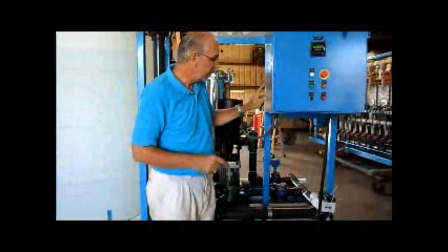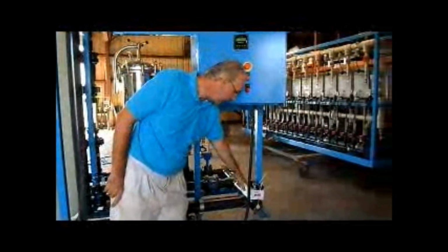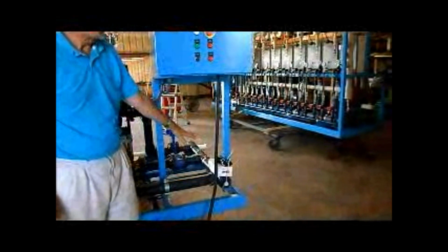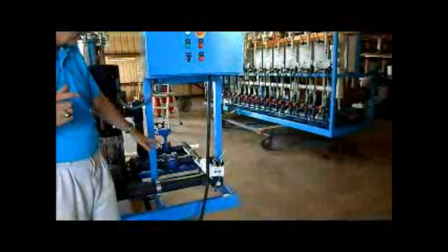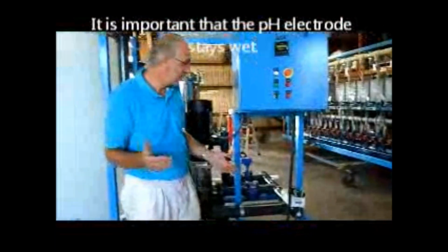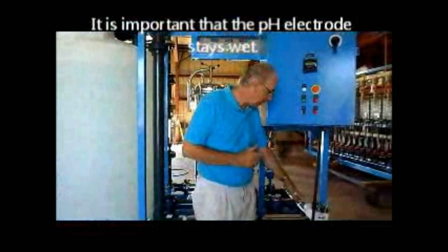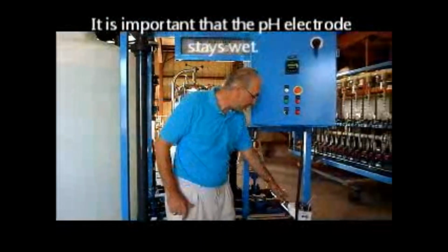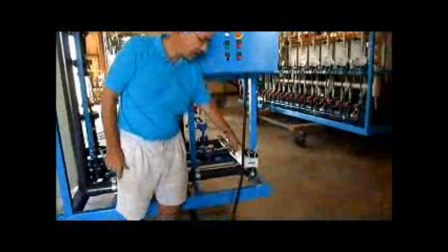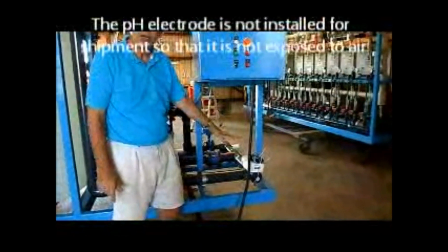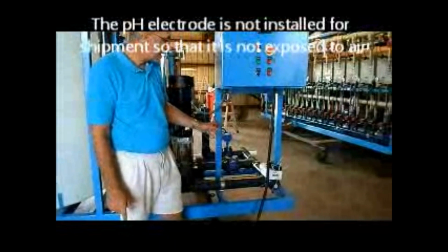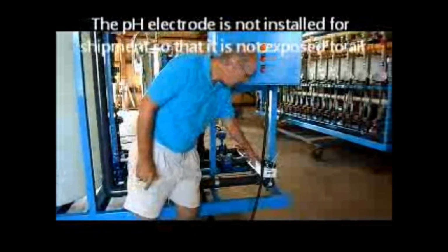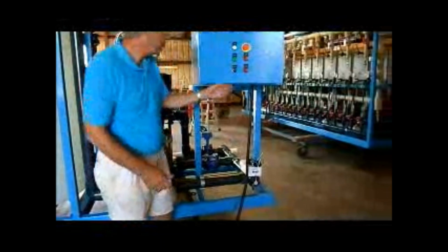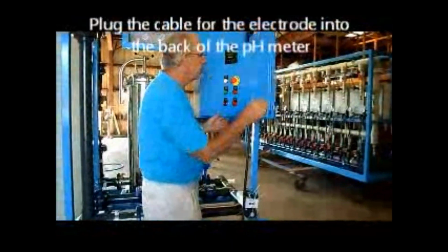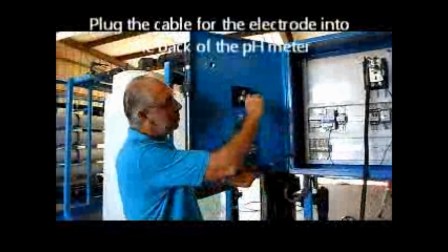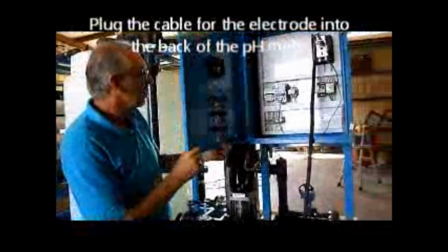For installation purposes, it's important to know that these pH electrodes are consumable. Once they get exposed to the air, they have a useful life of 6 months to a year. It's important that the pH electrodes stay wet. So when we ship the equipment, the pH electrode is not installed because we don't want it to be exposed to the air. When you get to the job site and you install and you're ready to clean, then you should put the pH electrode in right here and plug the cable into the back of the meter right here. Okay?